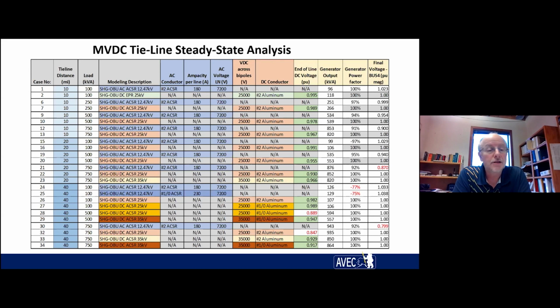You can see from here we did 10 miles, 20 miles, and 40 miles, and there are some breaking points. It's a busy table, but if you look at rows 24 and 25, that's at 40 miles with 100 kVA, looking at the 12 kV option, which is not a great option. You can see the genset is basically trying to support the voltage and providing VARs to the point that it can't, so that's not a great option.